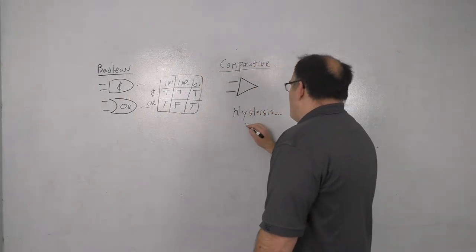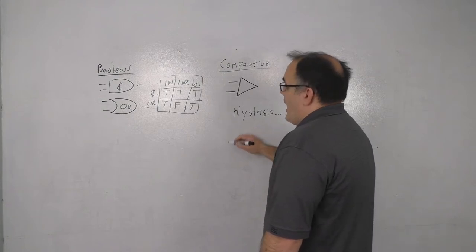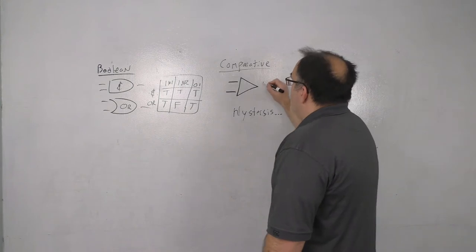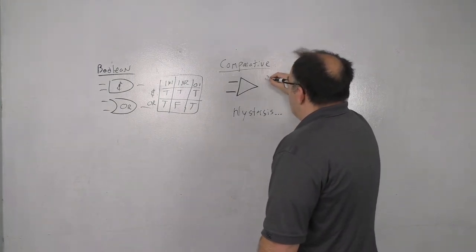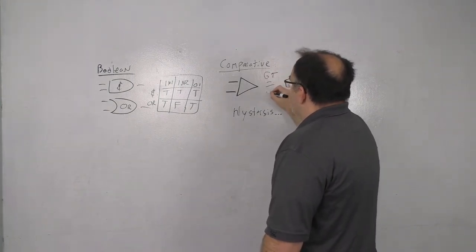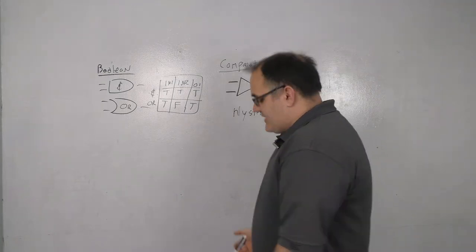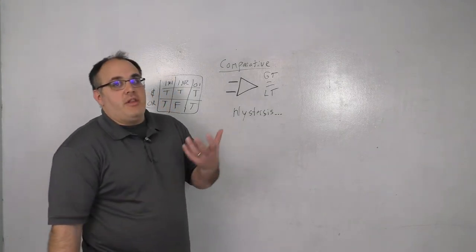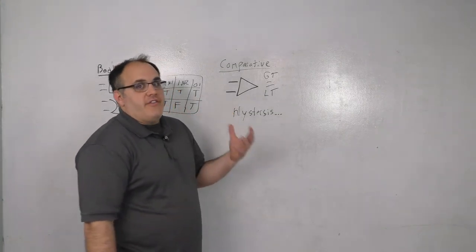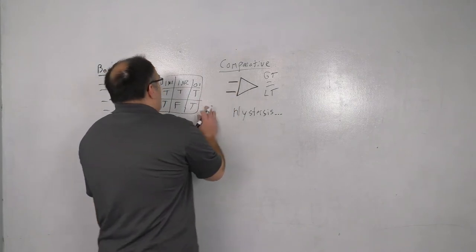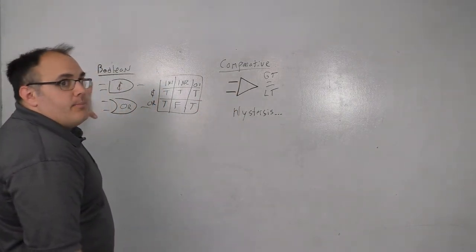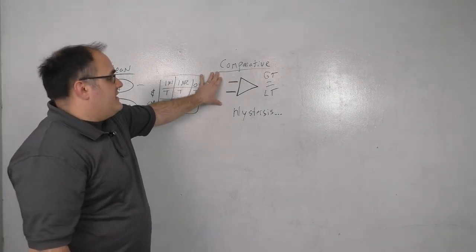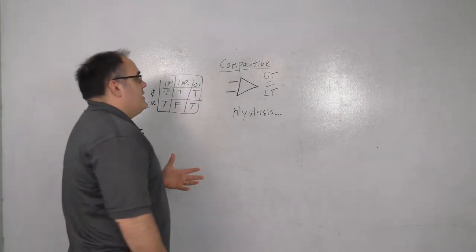There's a fancy block called a hysteresis, which actually has an up and a down. I'm not going to go through that here. It's kind of a more complex block. But comparators, you have kind of three types of comparators: greater than, equal to, or less than. And this is what's going to drive a lot of your switches. This is what's going to enable a lot of your PID loops. This is what's going to drive a lot of your logic. Basically, whereas Boolean blocks take Boolean values, these are taking integers and floats and doubles and decimals, basically numerics.